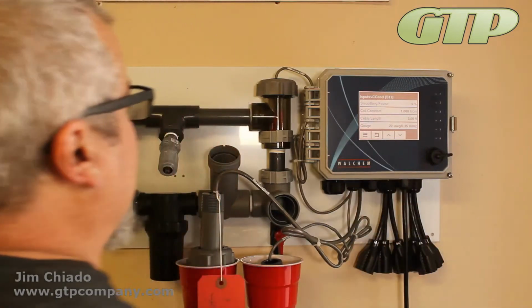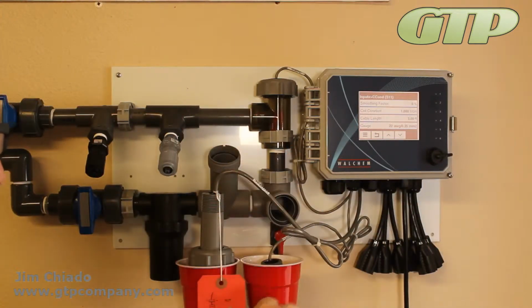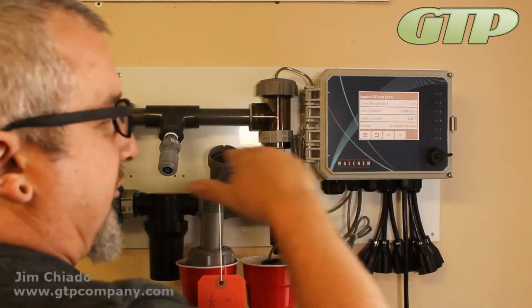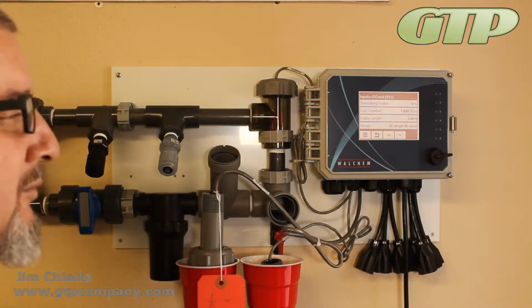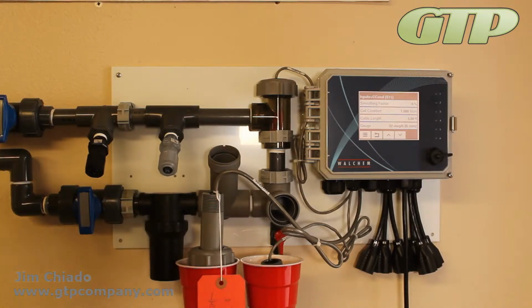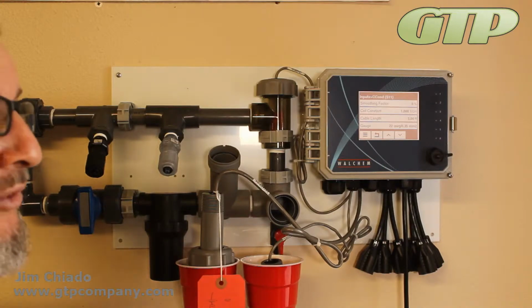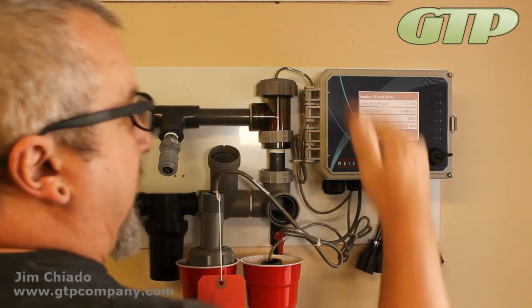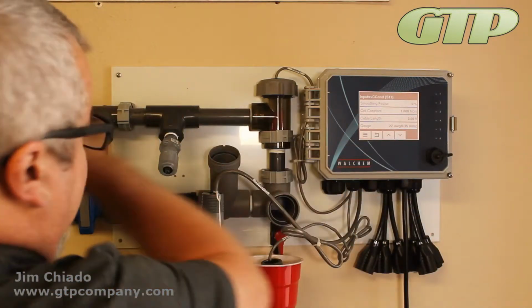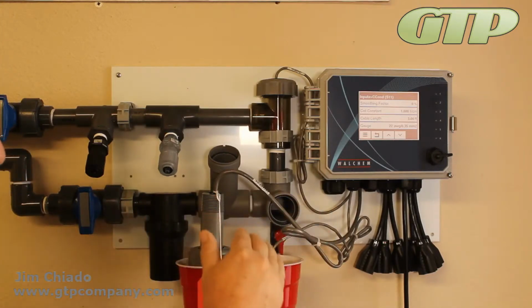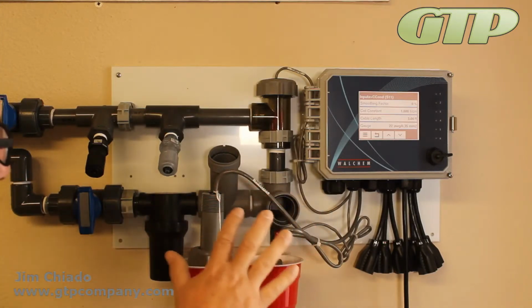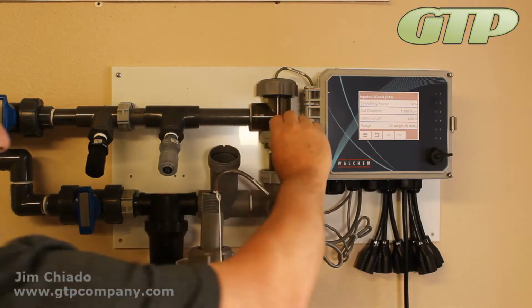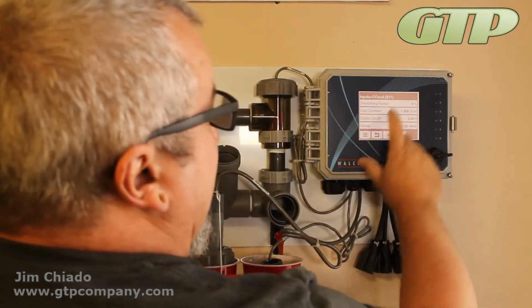Smoothing factor: when we walk up to a machine, we'll see it jumping around. Smoothing factor just helps smooth out that signal when you or the client come up here and look at it. You can see it move 5, 10, 20, maybe even 30 microsiemen, and it does jump around back and forth because of how fast the flow is going through here. Flows faster, it jumps around a lot more; it's a little bit more slow, it's a lot more lethargic, but that's what that smoothing factor is for.